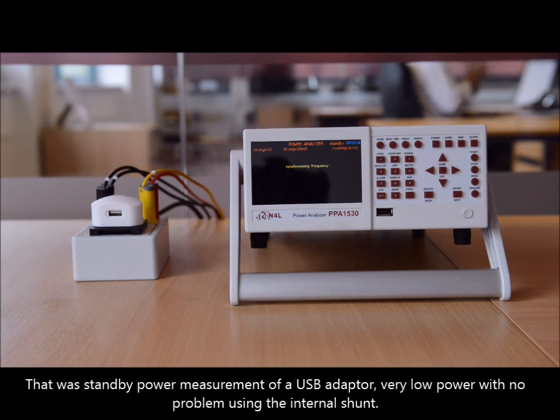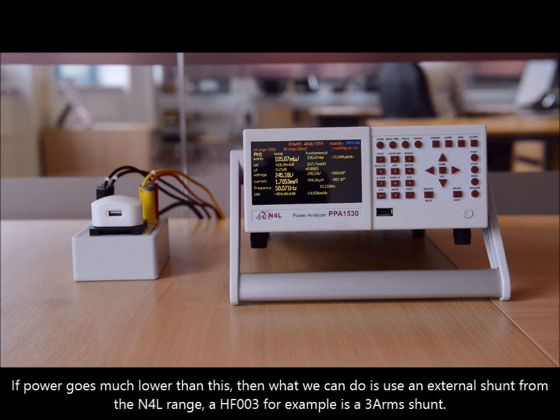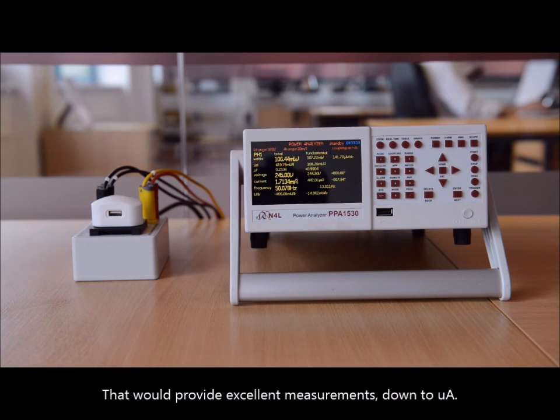So that was the standby power measurement of a USB adapter — very low power with no problem using the internal shunt. Now if powers go even lower than this, what we can do is use an external shunt from the N4L range. The HF003, for example, is a 3 amp rms shunt and would provide excellent measurements down to microamps.